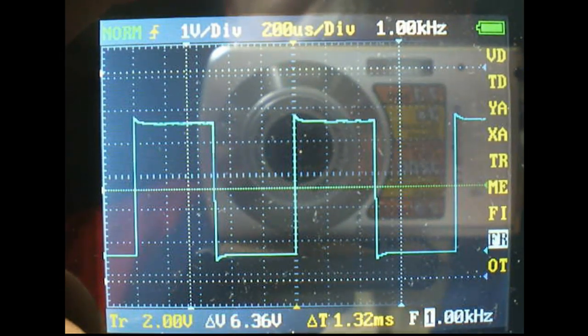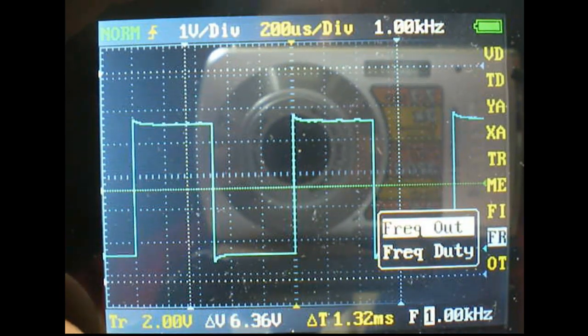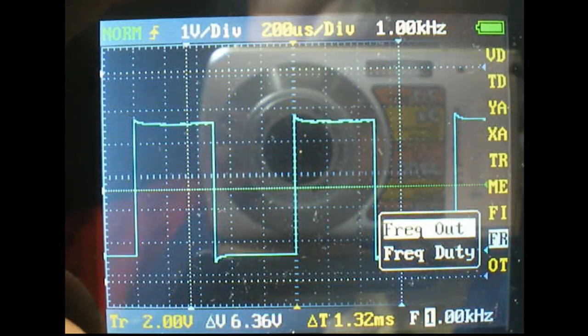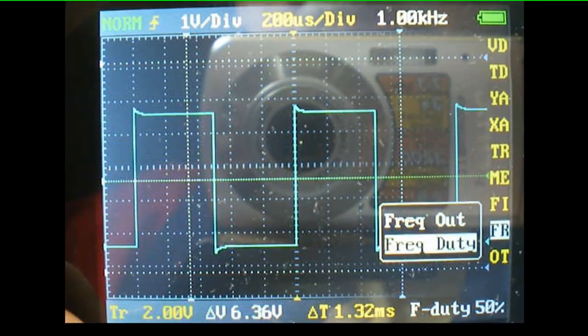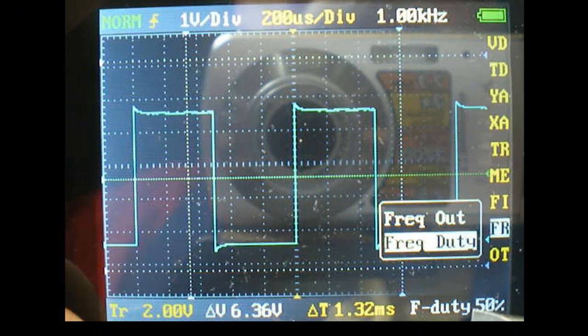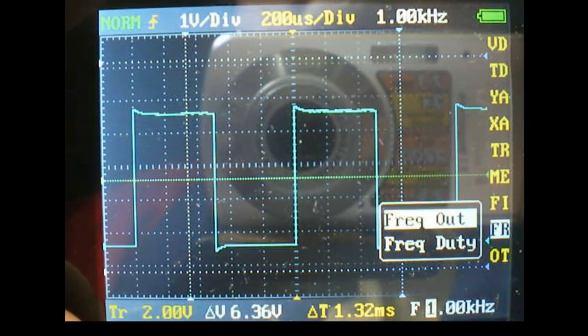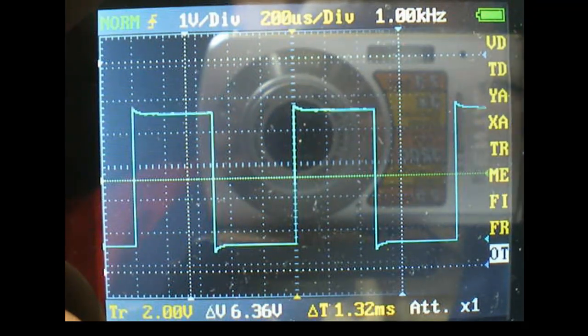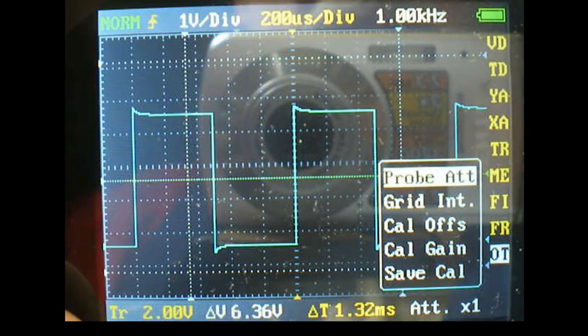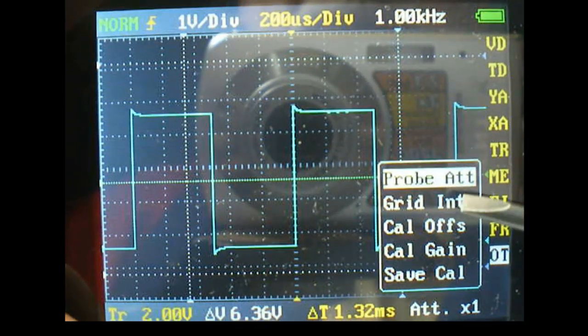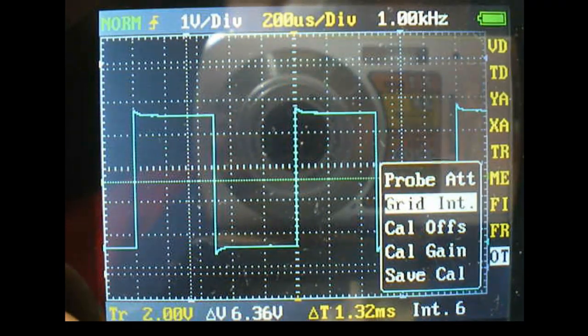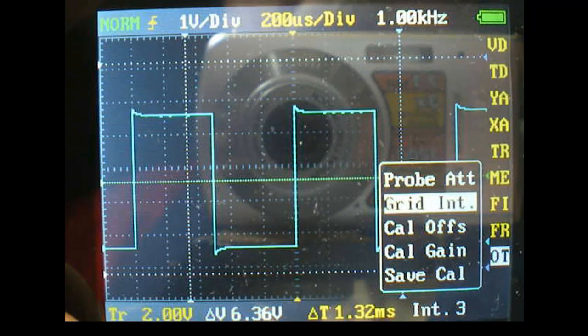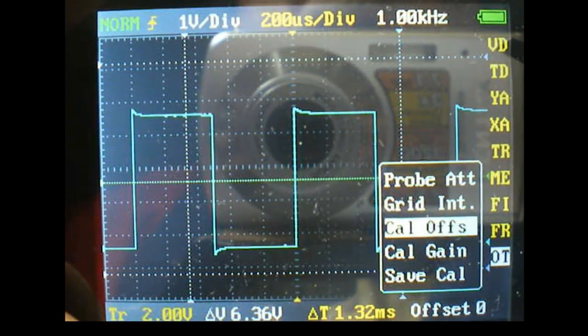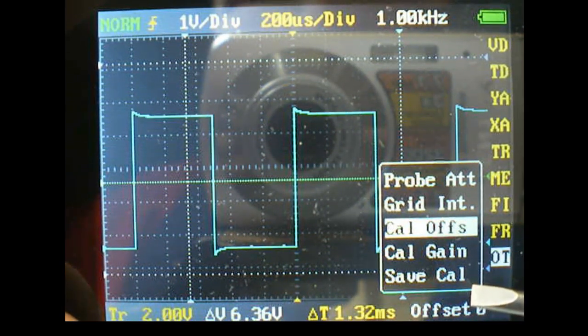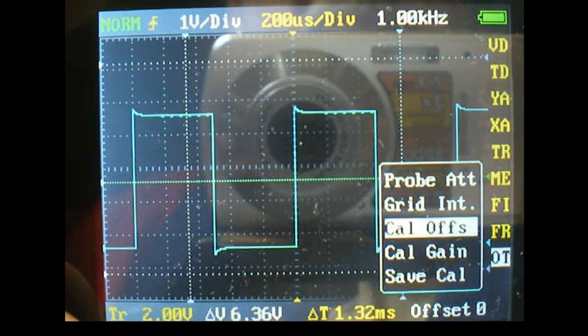Down here under the frequency output, that's the actual probe compensation signal, and we can vary the frequency output, and we can also vary the frequency duty cycle. And down here at the bottom is where it shows those changes that we make. We also have the ability to change the probe attenuation, which is down here right now. It's times 1, times 10, times 1. Our grid intensity, which you can probably see. And each volts per division step has its own calibration of offset and gain. And we can save those calibrations of offset and gain into permanent memory, non-volatile memory.